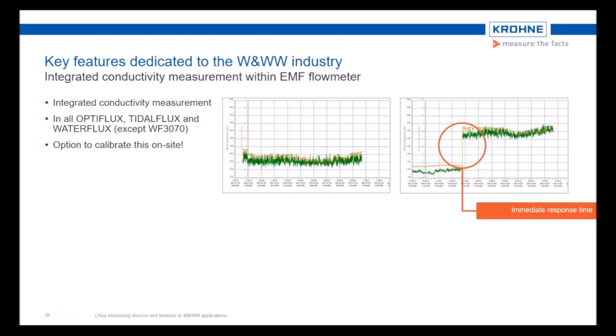The settable measuring range of the conductivity is 0 to 50,000 microsiemens per centimeter. We therefore cover almost all water types and qualities. A recalibration of the flow and conductivity measurement is not necessary. Furthermore, an on-site calibration of the conductivity measurement is possible. So this enables an exact compensation of the local conditions under consideration of the local environment.